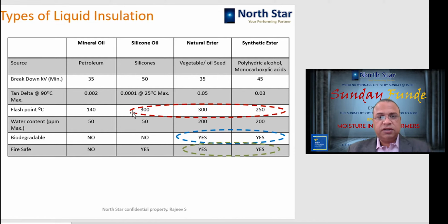Silicone oil is very good, because its flash point is 300 degrees centigrade as compared to natural ester and synthetic ester. But it cannot take much water. 50 ppm is the maximum limit which it can absorb, similar to mineral oil. Okay, and it is not biodegradable, but yes, it is fire safe.